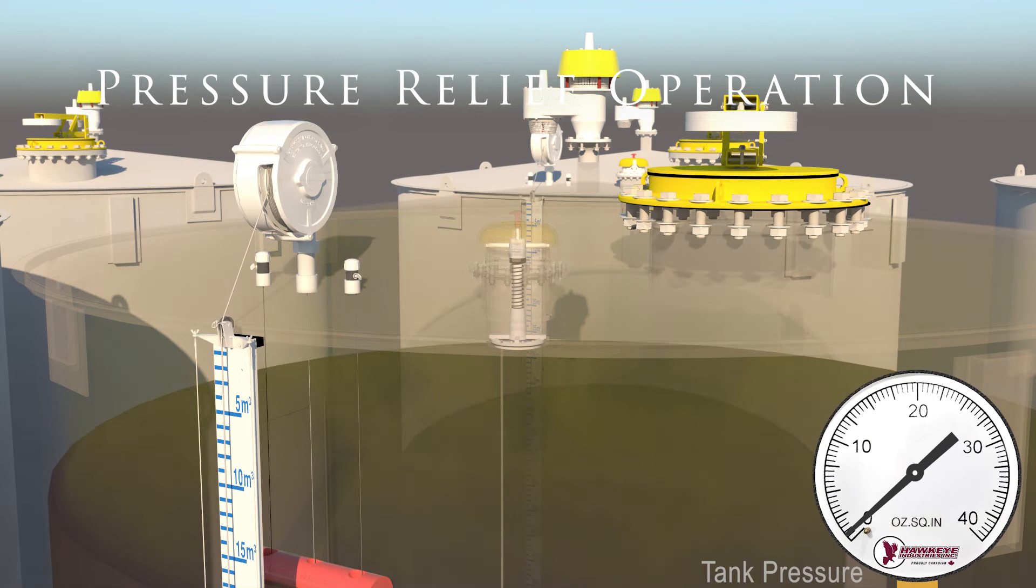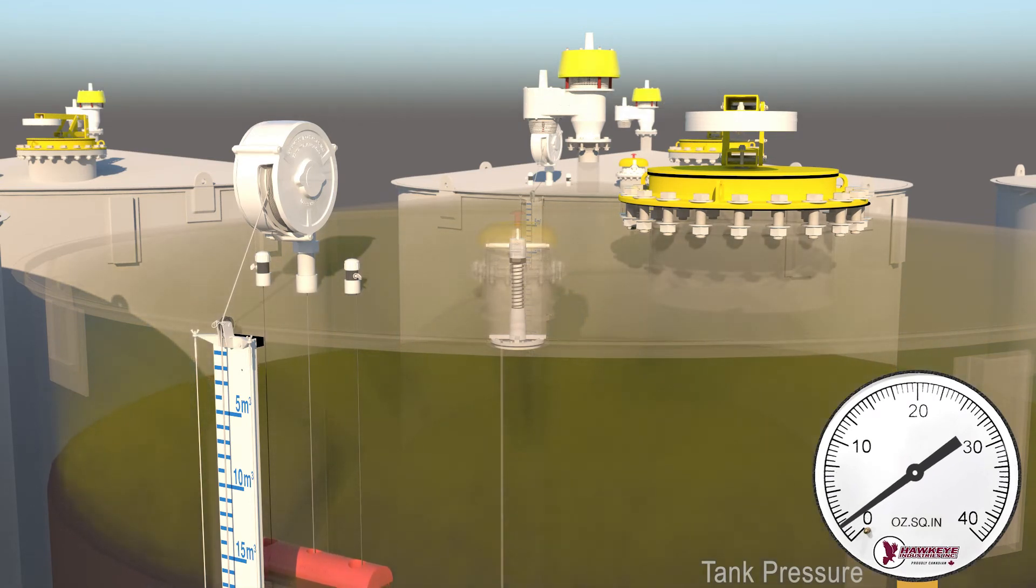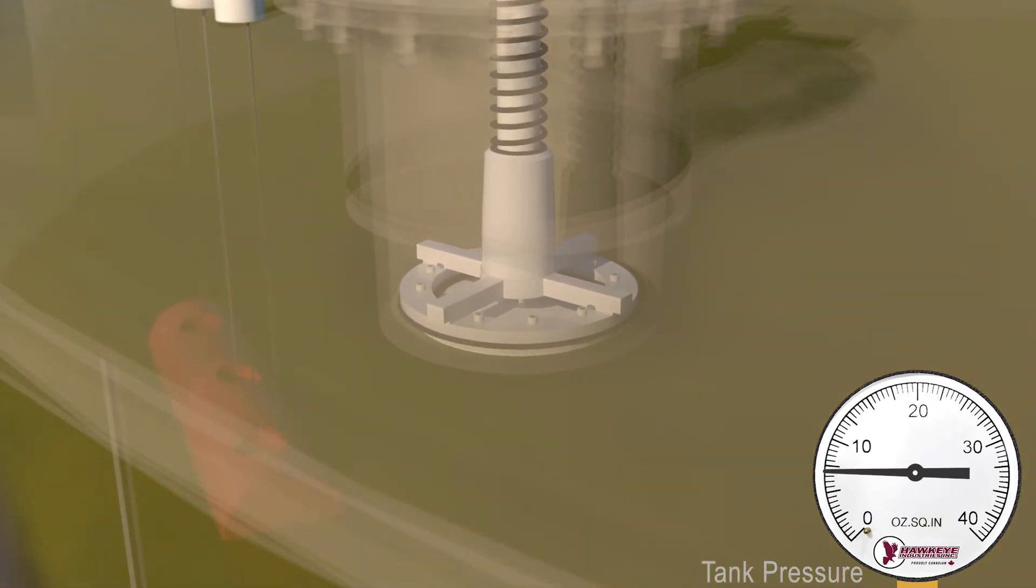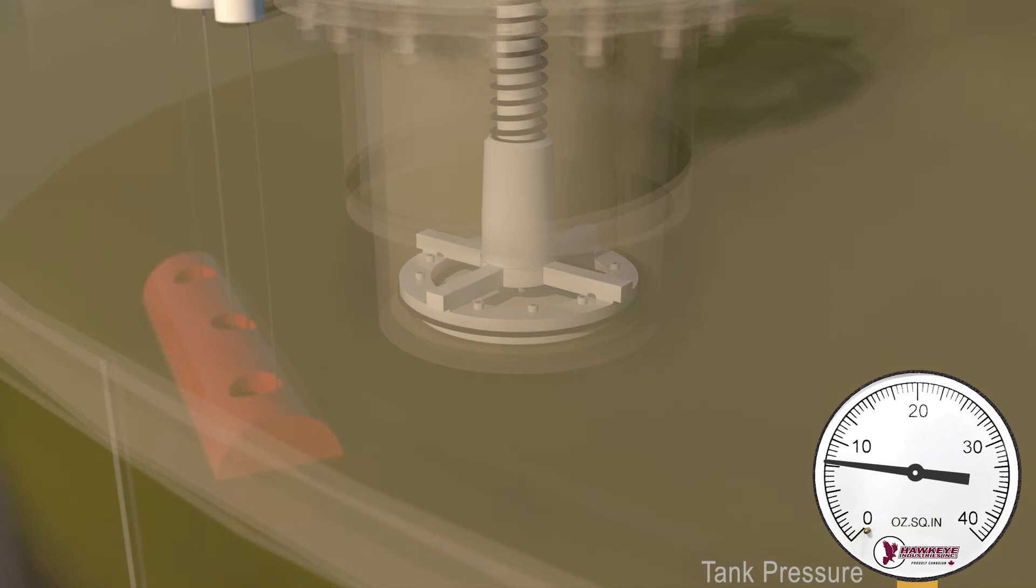As fluid flows into the tank, the internal pressure increases. In order to reduce emissions, the spider cage must not lift prematurely or leak below its set pressure. When tank pressure exceeds the 6 ounce per square inch set pressure, the spider cage lifts and allows gas from the tank to escape.